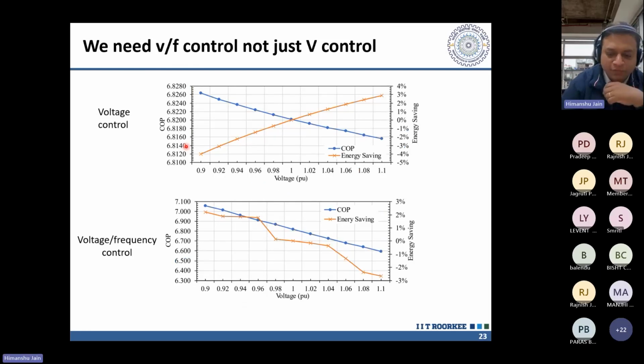So here's what we found through our simulations. When we do simple voltage control, reducing voltage by 10% or increasing it by 10%, what you see is that energy savings are actually negative, meaning you end up consuming more energy as voltage is reduced. The COP also doesn't change much, changes are only in the second decimal place. So effectively, there was not much use in simple voltage control alone.